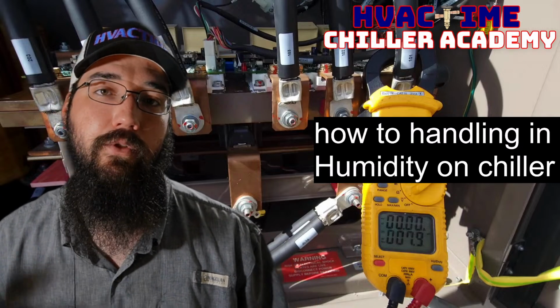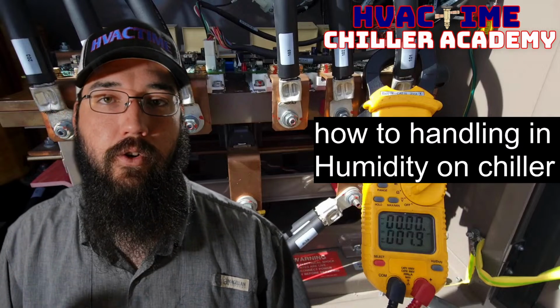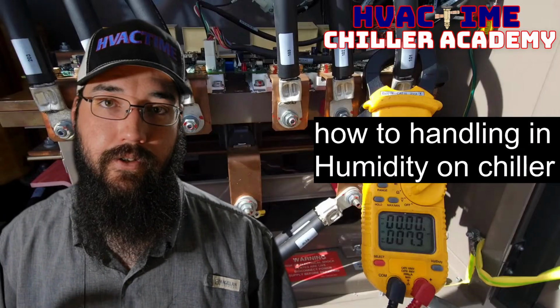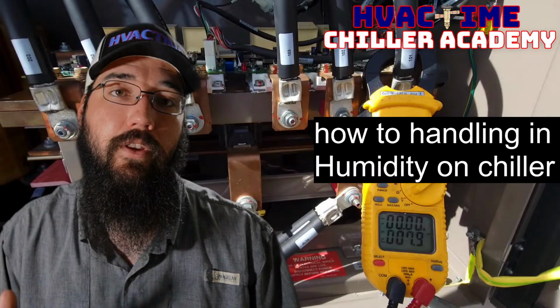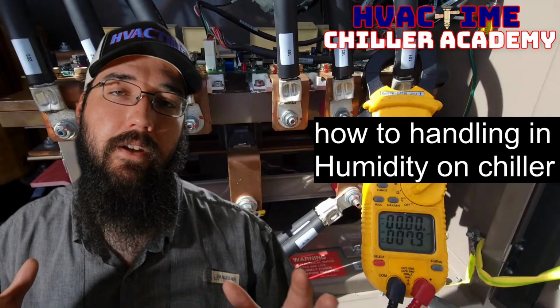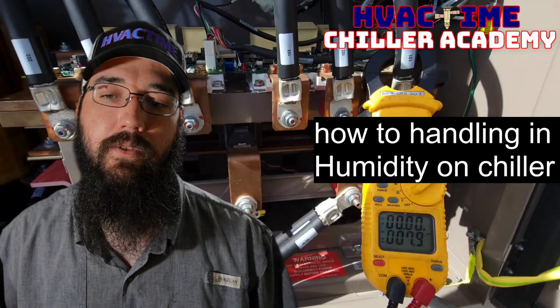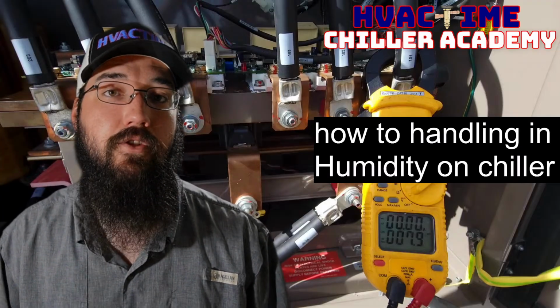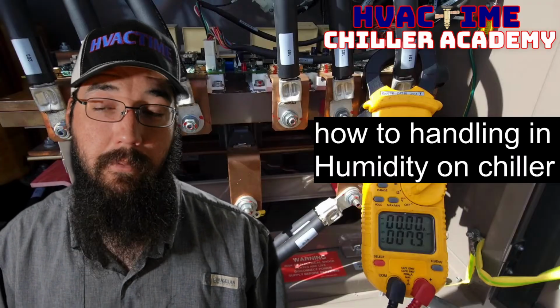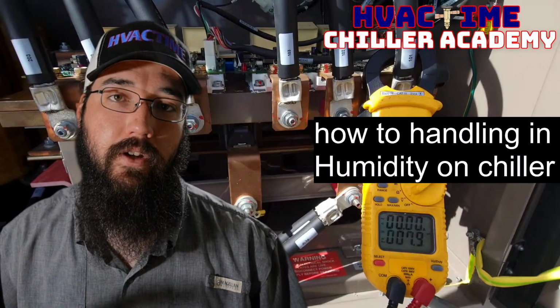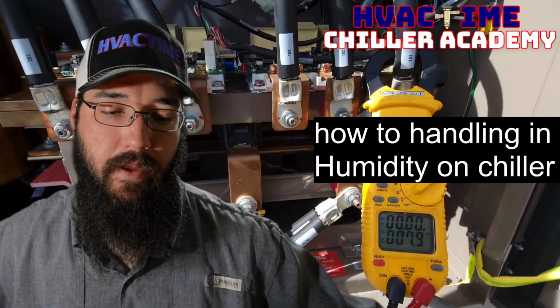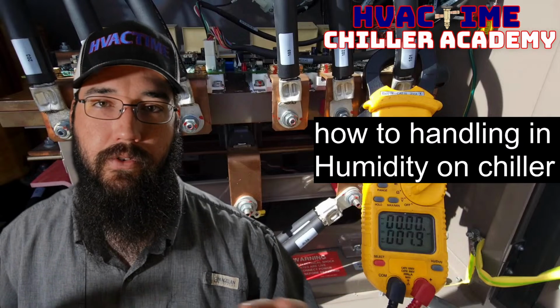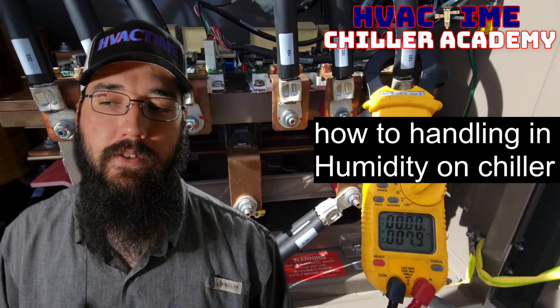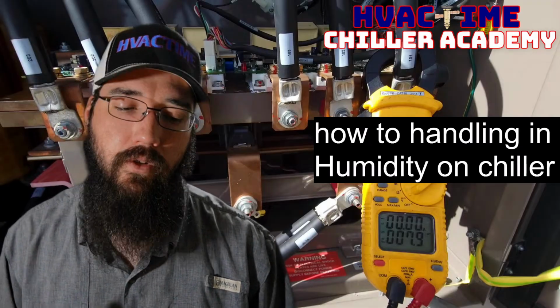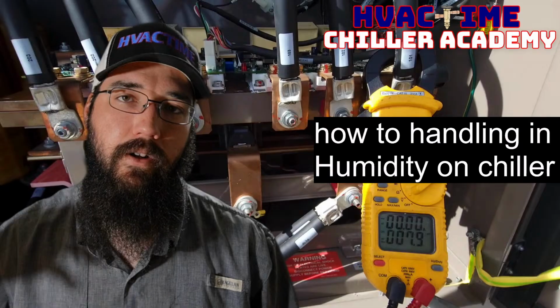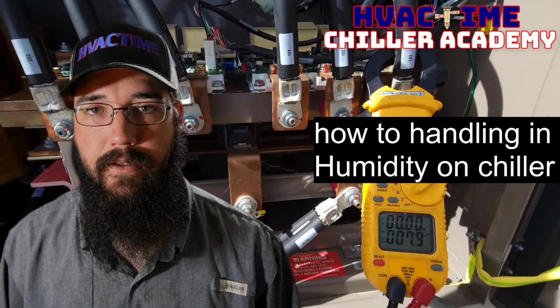And so then you just have to, depending on what your problem is, you can adjust either direction to achieve what you're looking for, so that you can make a better set point, because it's not always just an airflow issue on these systems. If you're having humidity problems and such, it's not just an airflow problem all the time. Now, many times it is. In my experience, most of the time, you adjust the airflow settings and you get the air distribution in the space correct, most of those humidity problems will kind of peter out. But sometimes it's just not always true. And so that's where adjusting that set point can be useful.